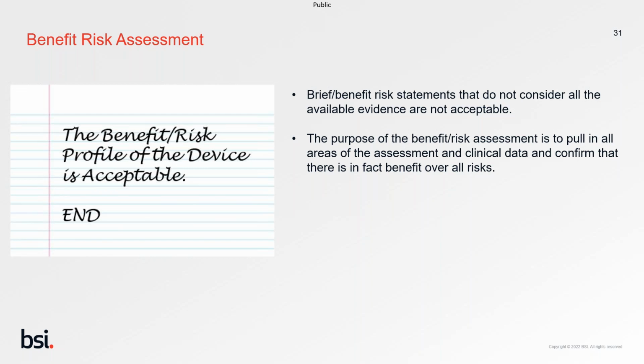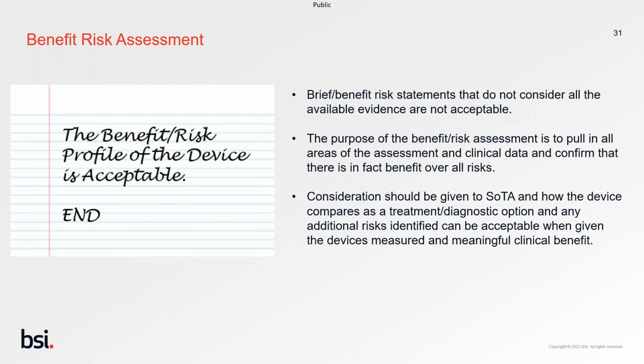And really what we're looking for is good, solid arguments that are presented within your clinical evaluation report. Within the benefit risk as well, it should be given to state of the art. How does your device compare to the treatment and diagnostic options that are still available? So where we started our clinical masterclass on the clinical evaluation plan, really bring through those objectives and demonstrate why your device is state of the art within your benefit risk profile, and demonstrate why it's acceptable.